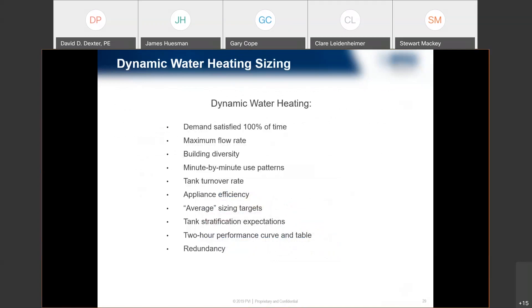So, what is dynamic water heating design? We want to make sure demand is taken care of 100% of the time. We're taking into consideration the maximum flow rate, but also building diversity in how that building uses water — which can change throughout the hour. At the same time, we want to make sure we don't have too big a tank where we're not turning that water over. Tank turnover, especially from a medical design standpoint, is very important — we need to turn that tank over multiple times an hour. Efficiencies matter, and redundancy factors need to be considered.